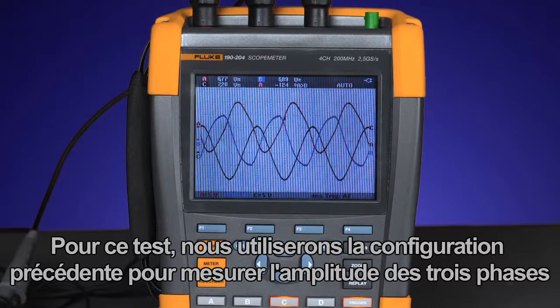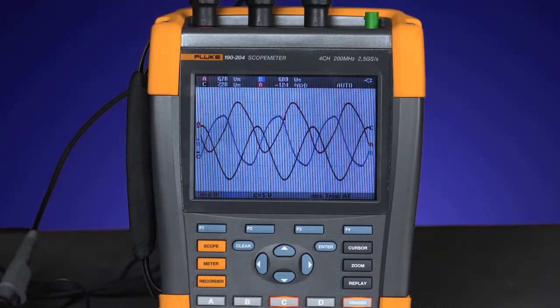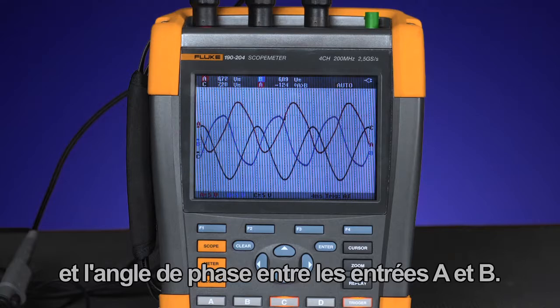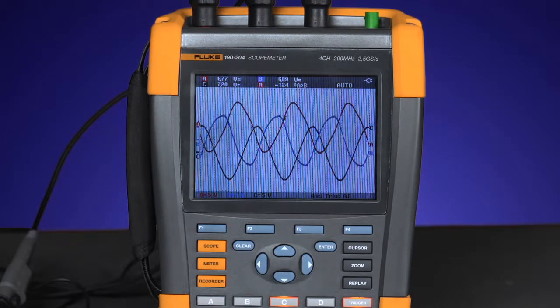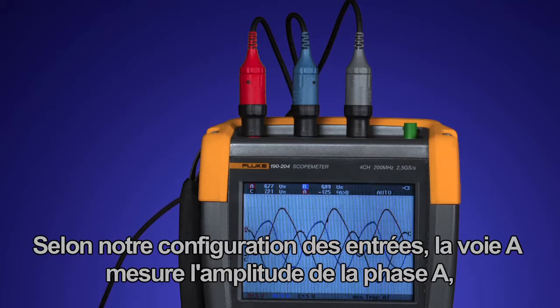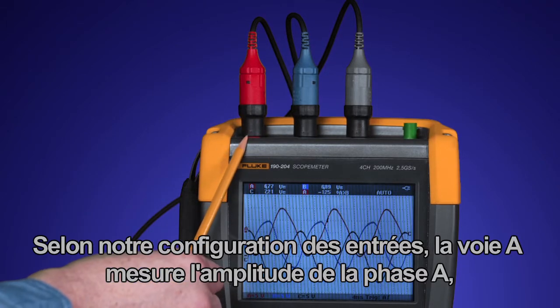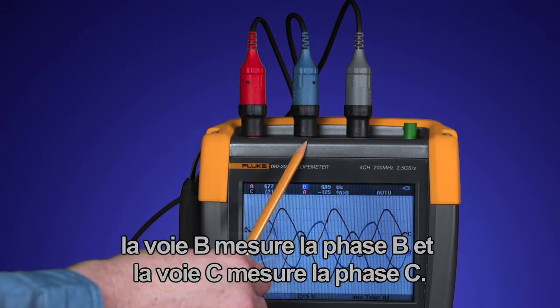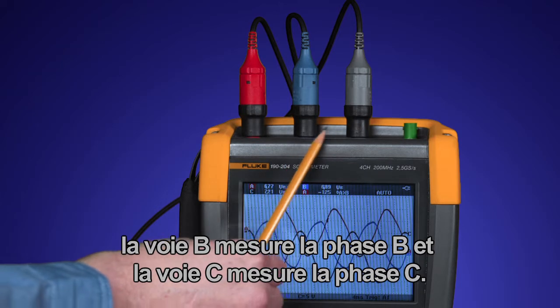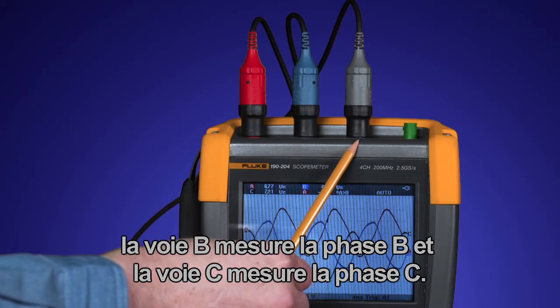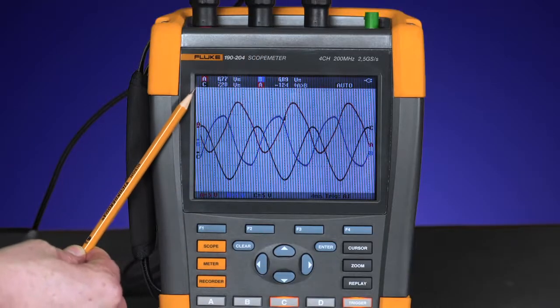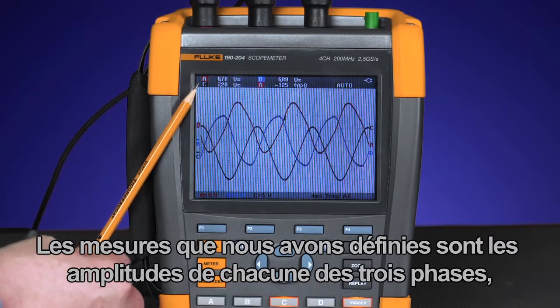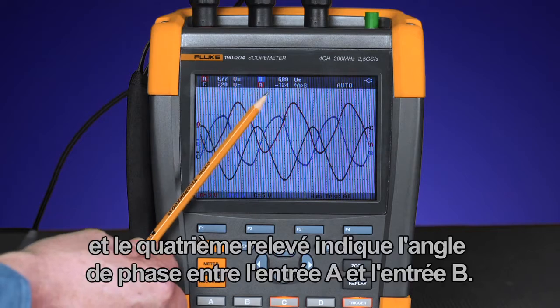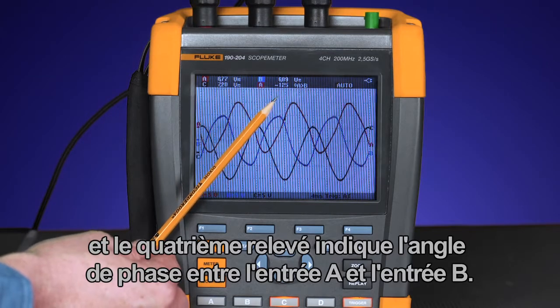For this test, we'll be using the previous setup to measure the amplitude of the three phases, as well as the phase angle between input A and B. We have our inputs set up with channel A measuring the amplitude of phase A, channel B measuring phase B, and channel C measuring phase C. Our defined measurements are the amplitude on each of the three phases, and the fourth input reading the phase angle between input A and B.